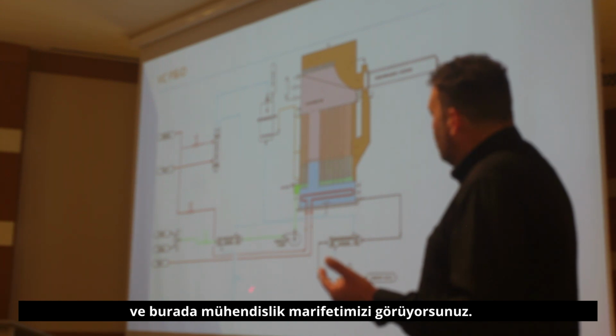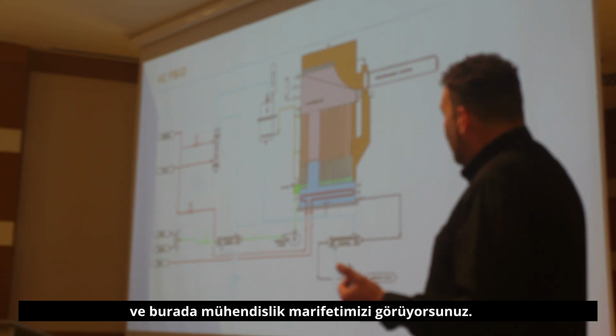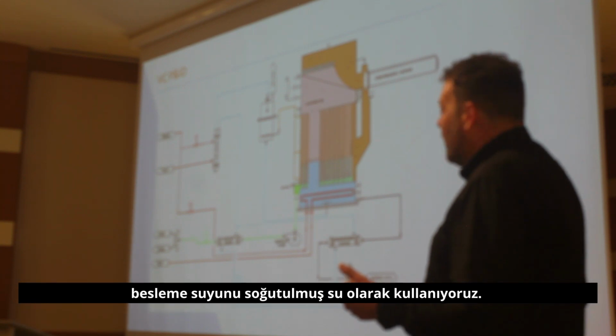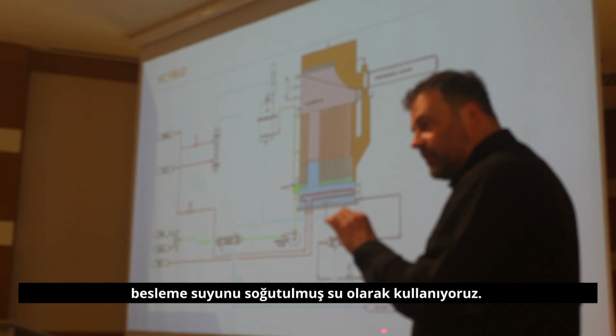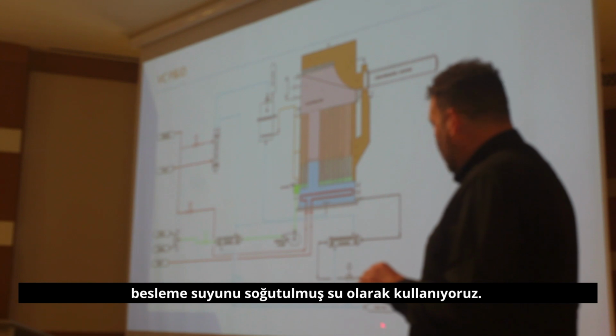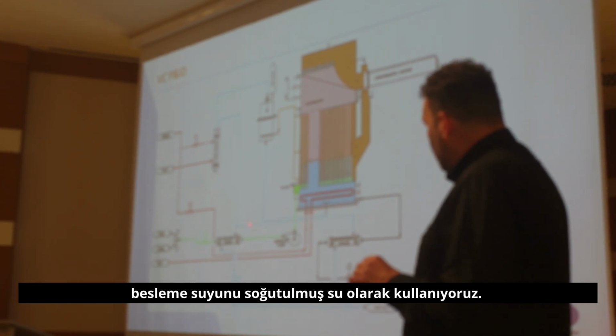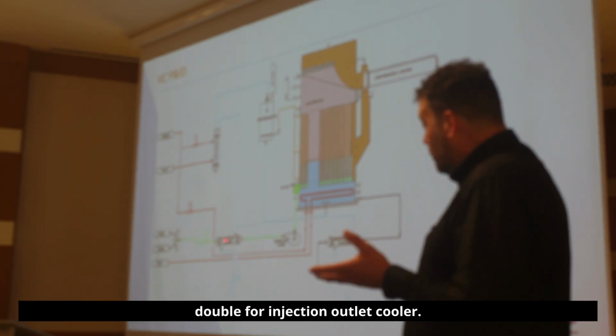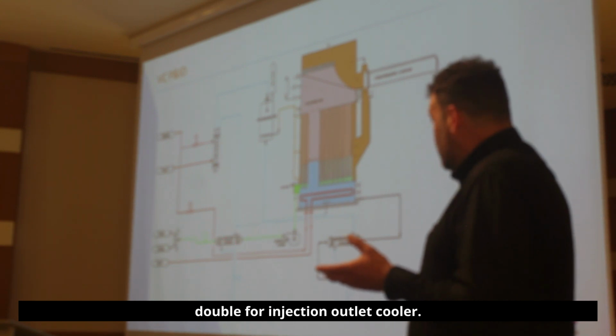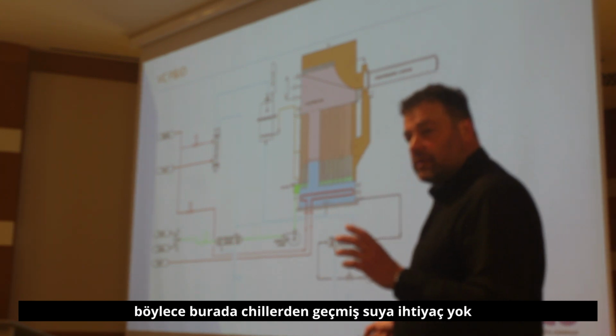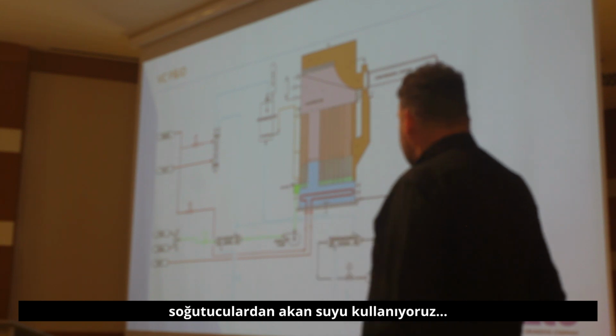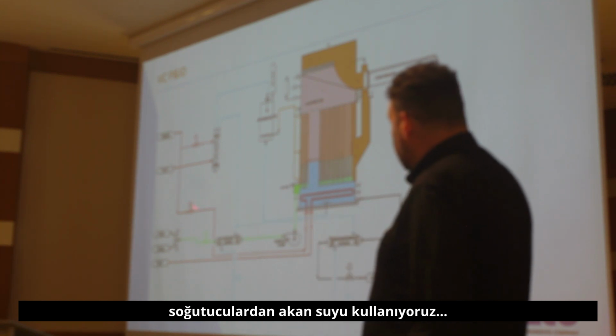Here we already see one of our engineering tricks. We use our feed water as chilled water for our blowdown cooler and our distillate water for injection outlet cooler. So there's no chilled water needed for this, we're using our feed water and running it right through the coolers.